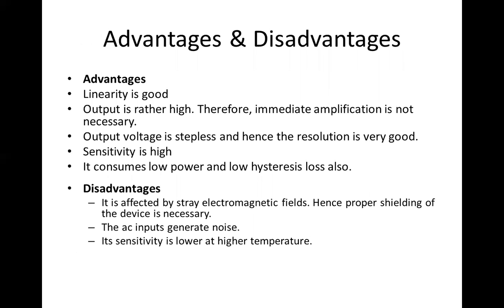Now, everything has its own advantages and disadvantages, so LVDT also has. The advantages: linearity is good, output is rather high, therefore immediate amplification is not necessary. Output voltage is stepless and hence the resolution is very good. Sensitivity is high, it consumes low power and has low hysteresis loss also.